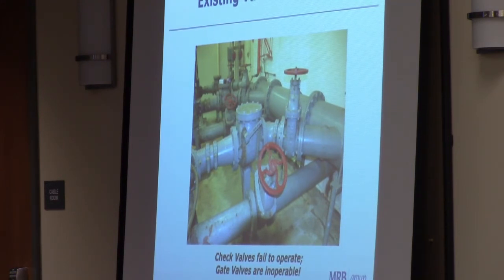So as part of the overall plan to rebuild the station, we would take all that piping out, take the pumps out, and replace them. On the suction side, that's an 8-inch diameter pipe, and based upon our evaluation, we have determined that it should really be a 12-inch pipe. The nice thing about putting a 12-inch pipe in there is that we can cut out and core out a 12-inch pipe and put a new 12-inch pipe in there with a link seal and take away the leak problem we identified. So it's kind of a catch-22. You do it and you've solved really two problems.